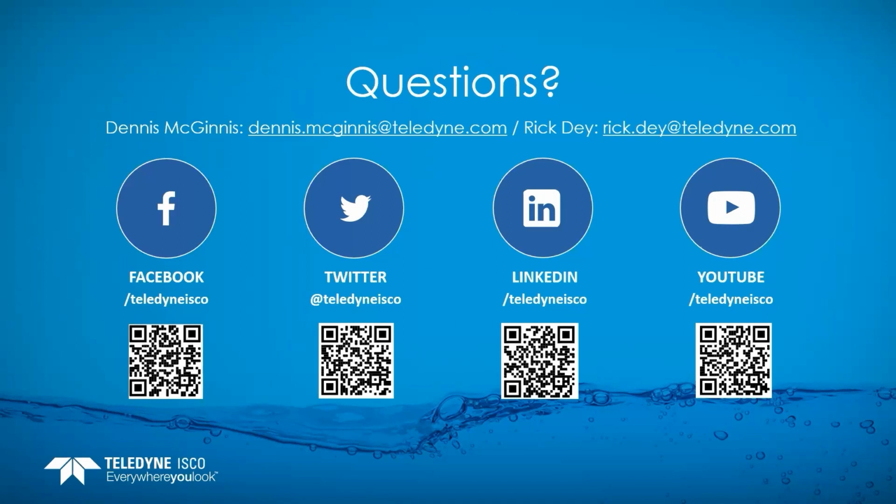Go ahead. The next one down is, is it possible to transmit data immediately if it crosses the threshold in the field? Yes. As Rick mentioned, you can set up your primary frequency, and the fastest that would be is 5 minutes to push. But typically you could have something slower, like 15 minutes. In this case, could I make it transmit immediately? Yes. In our meters, whether it's the Signature, the DuraTrack, or 2100, you can set up what we call a server alarm. What that does is you can set up an equation that says, when this threshold is met, go ahead and push the data immediately to the server.